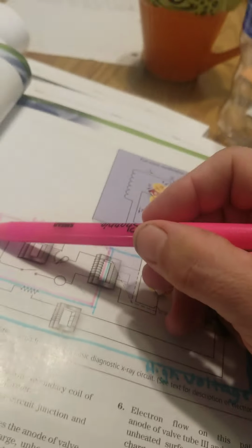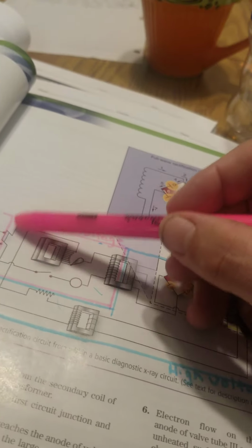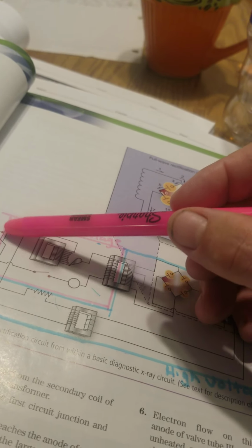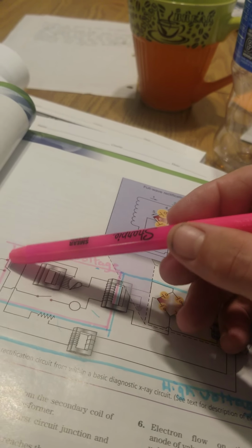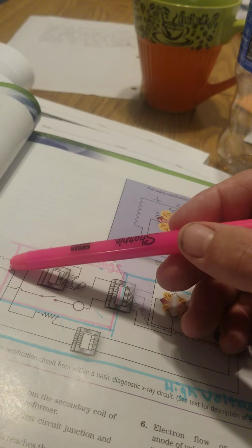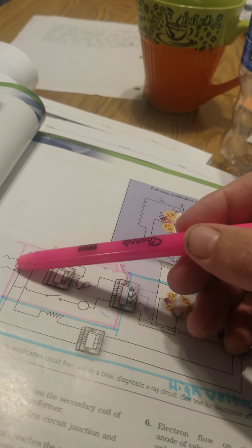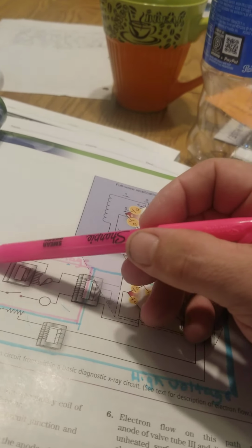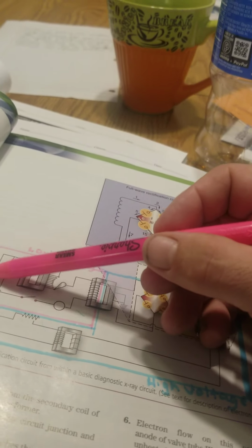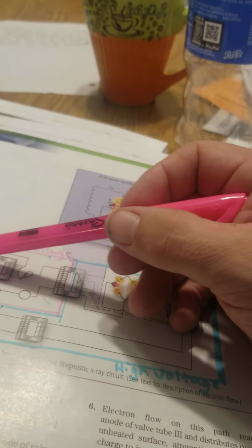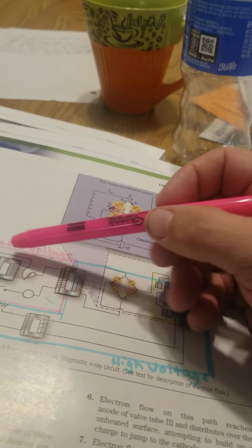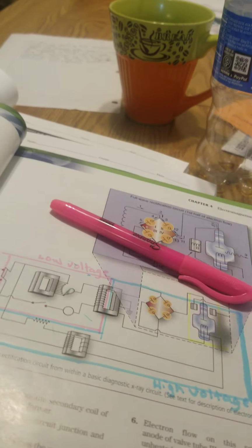First thing that we do, though, is we got to get some power to power this device, and that's coming from our electric company right here. Through the wall outlet is plugged in, or wired in, I guess, through a breaker. And the breaker is coming in the power at 210 to 220 volts of electricity. And that is not going to be enough for us to make an X-ray. We deal with kilovolts, so we're going to have to step it up in power anyways.